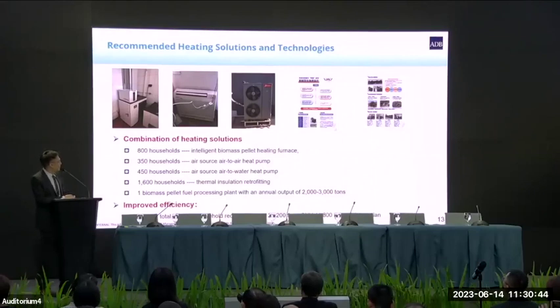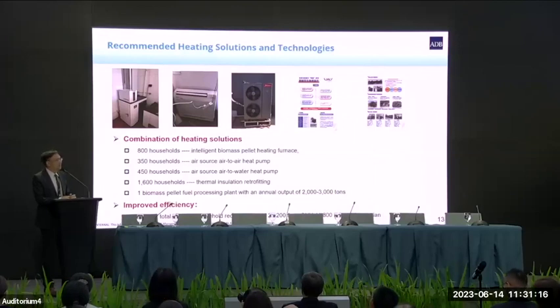Most importantly, we proposed a combination of heating sources and solutions after doing surveys and piloting in several households and villages. We propose that 800 households use intelligent biomass pellet heating furnaces, 350 households adopt air-to-air heat pumps, and 450 households use air-to-water heat pumps, with all 1,600 households adopting thermal insulation retrofitting. To provide fuel for the biomass furnaces, we also propose building a biomass pellet plant with an annual output of 2,000 to 3,000 tons. With this combination of measures, we can reduce the cost from 41,000 to 21,000 yuan.